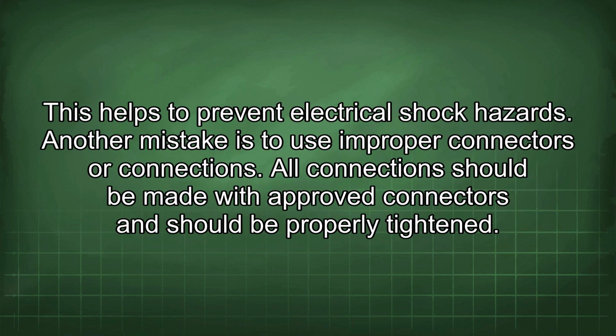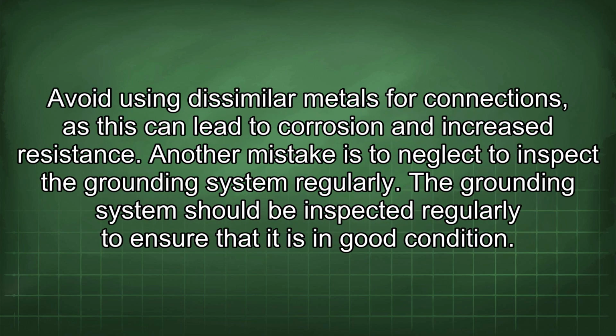This helps to prevent electrical shock hazards. Another mistake is to use improper connectors or connections. All connections should be made with approved connectors and should be properly tightened. Avoid using dissimilar metals for connections, as this can lead to corrosion and increased resistance.